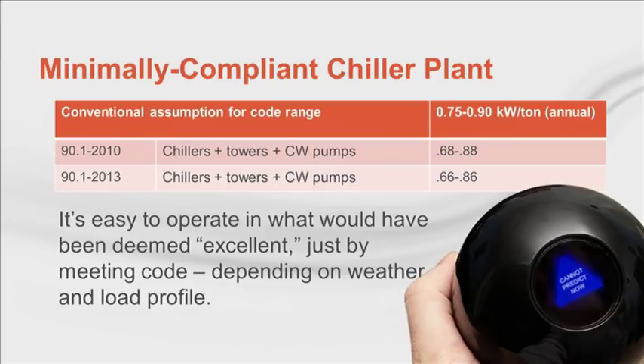Our models show that it's possible to be excellent, that is, below 0.7 annualized kW per ton, while only just meeting the code minimum requirements today, using constant speed chillers and a fixed tower set point. As Mike showed, significant improvement beyond the minimum code for chillers is available, both for full load and part load. But the vast majority of difference between high and standard performance chiller plants is earned in their design and control, in the ways that chiller plants, intentionally or not, deviate from the energy models. So that's what we'll be discussing next.